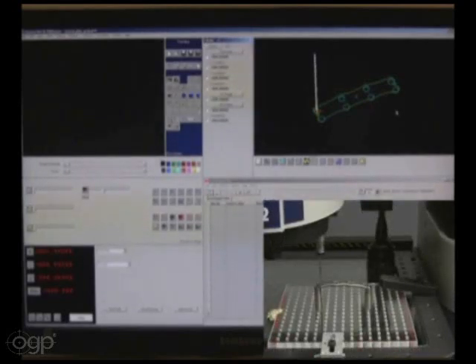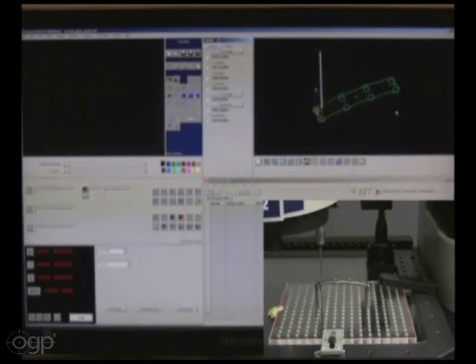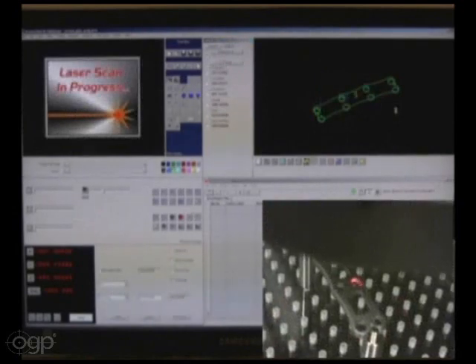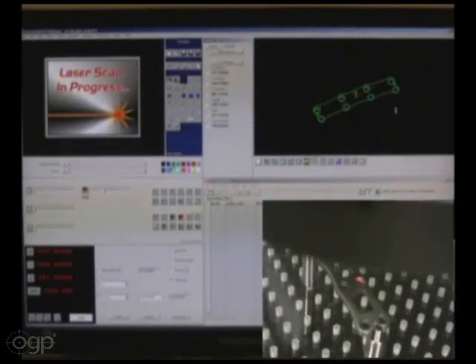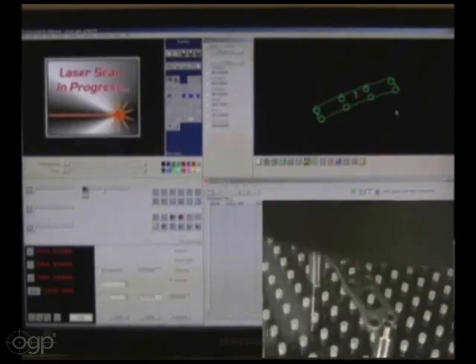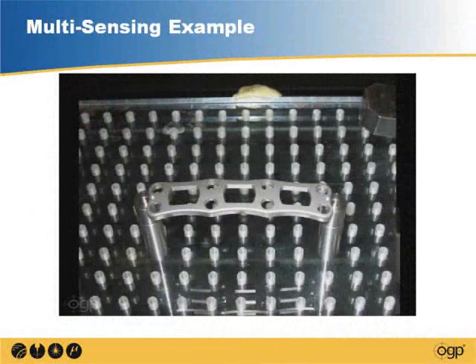Just went and picked up a touch probe, okay? This touch probe is necessary to get down into some of those holes and measure the diameter of those holes at a certain depth height. And so the advantage of a multi-sensing system is that you can take advantage of these strengths and weaknesses of the sensors. Here it's doing a laser scan around that kind of a spherical seating surface on that part, which can only be done with laser because you're taking a lot of data points on a very small arc segment on that sphere, and that's a significant challenge. But if you have a lot of data points with the laser and very accurate data points, then you're getting some good measurements out of it.